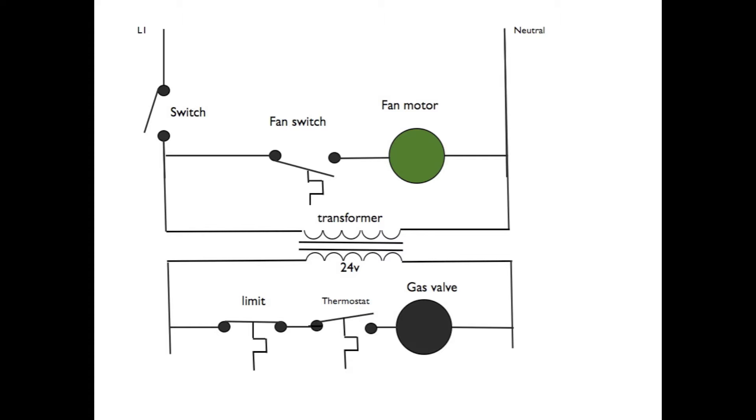Now, why do we use a 24-volt circuit? Because 24 volts is low enough that you're probably not going to get electrocuted off of it. The wiring can be lighter, and the controls are more accurate.